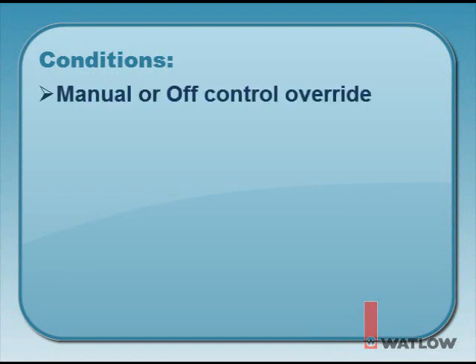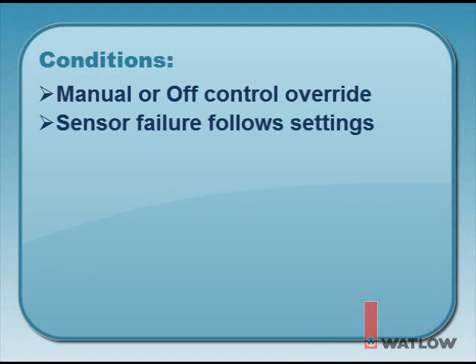There are conditions that alter the control mode. Some of these conditions are: a manual or off control mode override is requested via digital input, EZ key, or action function — these are programmable by the user. A sensor has failed, and the control mode changes to the user pre-programmed action.